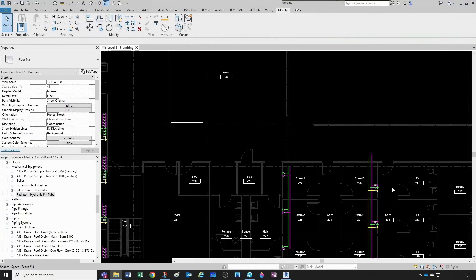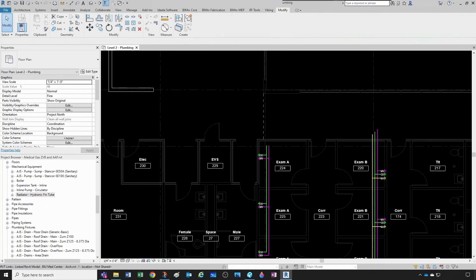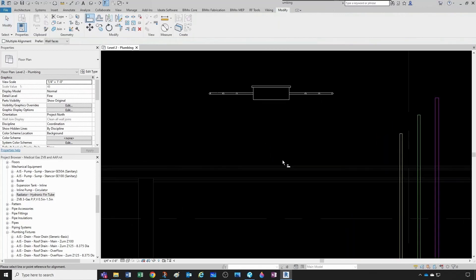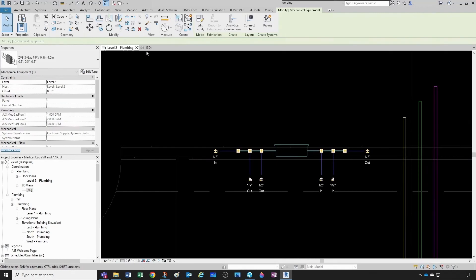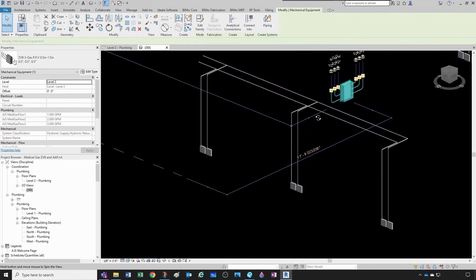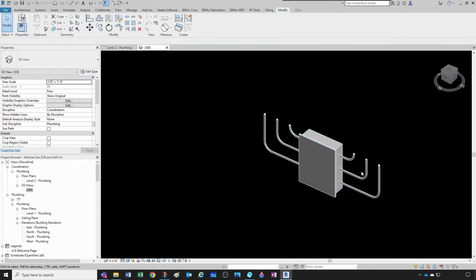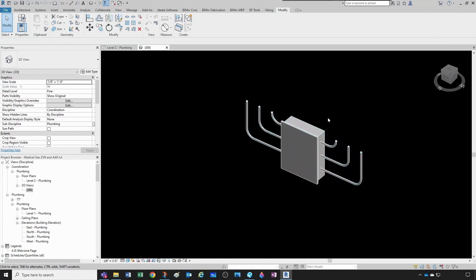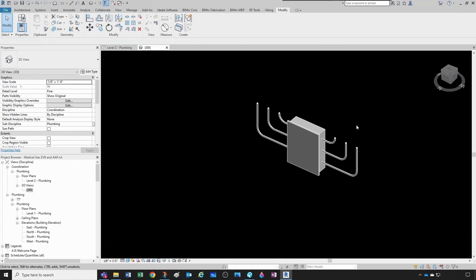Let's drop our first zone valve box, starting with Exam B which has three medical gases. I'm going to select a zone valve box with three gases — two of them are pressure and one is vacuum. I rotate this 180 degrees and align the exterior face of the wall to that little flange. The convention is: when facing the zone valve box from the front, entering pipes are on the left and exiting pipes are on the right — the demand side is always on the right, and the source side is on the left.